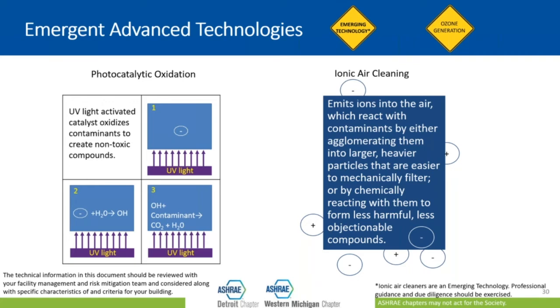The ionizing air cleaners are similar to the photocatalytic oxidation equipment. You want to be careful with these because one of the challenges here is that they can produce ozone, right? These are like the ionizing air cleaners that you may have seen in the past. They have a DC voltage that gets applied to the wires, and so they create the ionizing field. But instead of charging those particles so that they agglomerate into bigger particles that are then precipitated out, they actually send those ions out into the space where they continue to interact with the organic chemicals. So this too is a derivative technology. So you just want to be careful when you're using these.